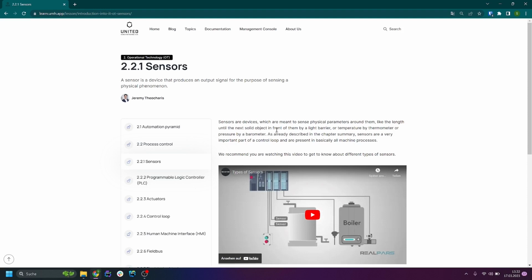And then you have a range of analog converters, which will try to adjust and normalize the signal. As an output of a sensor, you typically have a somewhat normalized signal, either 0 to 10 volt, 4 to 20 milliampere, or a digital signal.